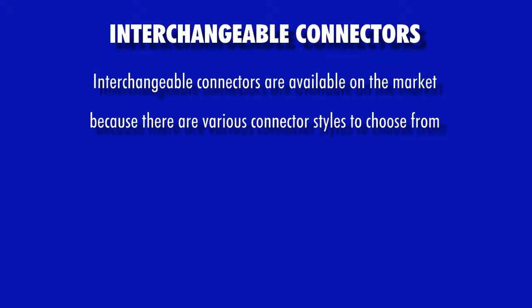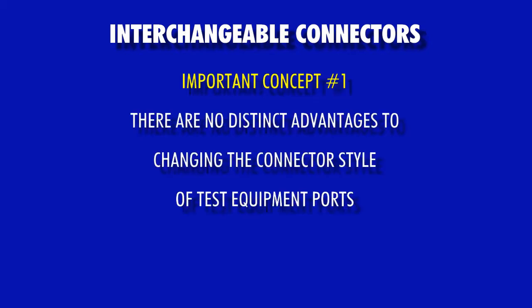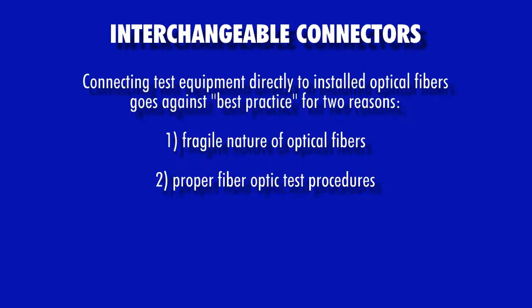The main reason why interchangeable connectors have found a niche in the fiber test industry is that there are many different connector styles to choose from. However, there are many fiber optics professionals, especially beginners, who may not realize that there are no distinct advantages to changing the connector style of test equipment ports. In fact, connecting an installed optical fiber directly to test equipment goes against best practice for two key reasons. First, the fragile nature of optical fibers, and second, proper fiber optic test procedures.